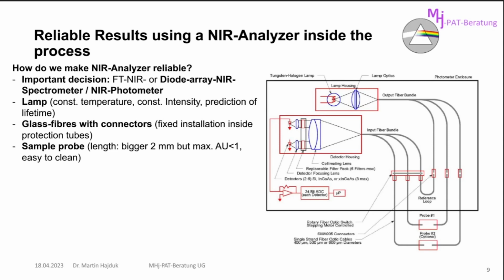So then we have the sample probe. In my opinion, it is very important that the path length is bigger than 2 millimeters, but we have to take care about the absorption maximum. It should be smaller than 1. That means a minimum of 10% of the light should go through the sample cell, in the area where we have the biggest absorption. So then we have the optical switch here. In former days, we had a mechanical optical switch, but nowadays I'm sure it's better to have an electronic part in this position without any moving parts.